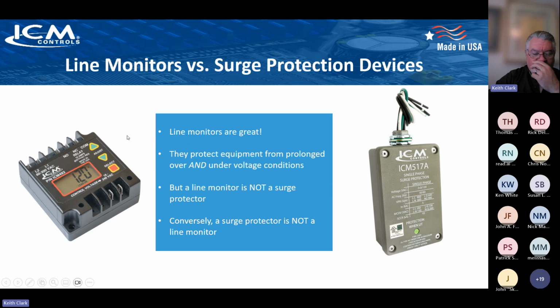Line monitors versus surge protection devices. And I'm throwing this in there because I think it's important to note that while the 517A is an awesome device, in my opinion, the best device out there in its class, it is a unique event. A surge like that is a unique event. So you're well protected from those surge events. But what if you have a brownout? What if you have an undervoltage condition? A surge protection device, anyone's surge protection device, is not going to do anything for you in that circumstance.